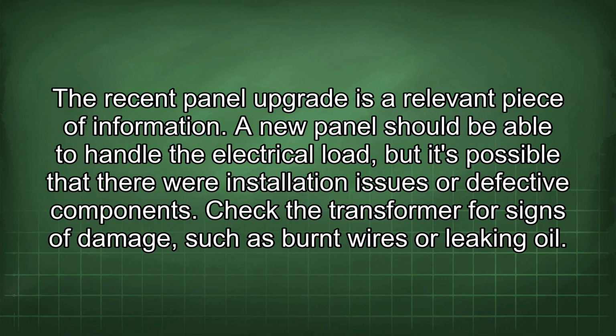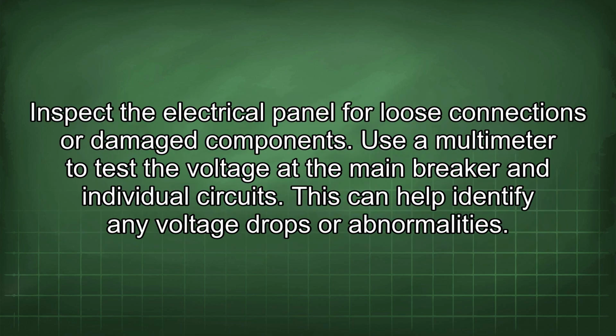A new panel should be able to handle the electrical load, but it's possible that there were installation issues or defective components. Check the transformer for signs of damage, such as burnt wires or leaking oil. Inspect the electrical panel for loose connections or damaged components. Use a multimeter to test the voltage at the main breaker and individual circuits. This can help identify any voltage drops or abnormalities.